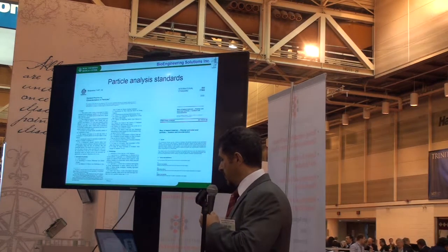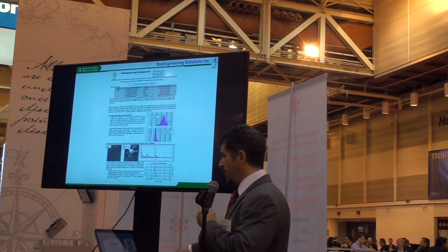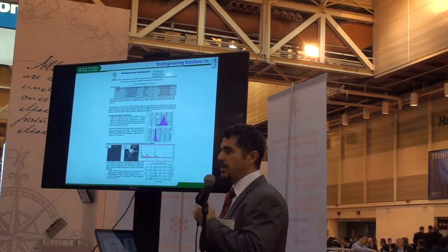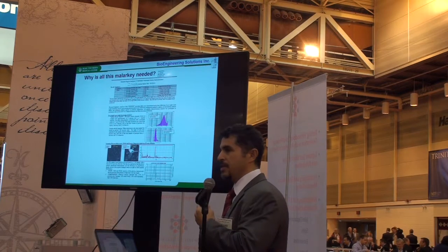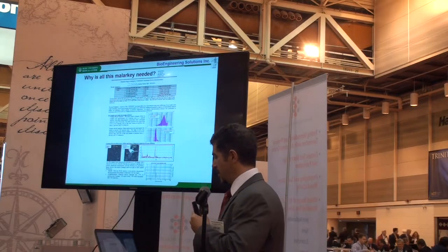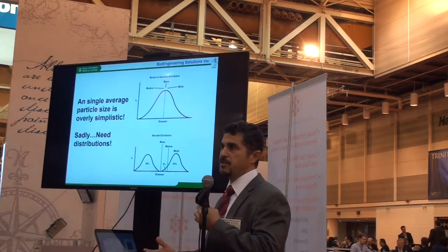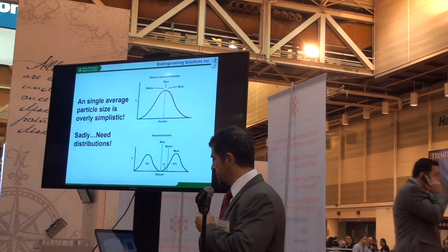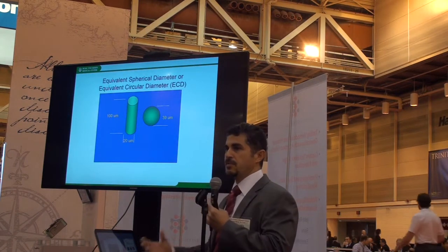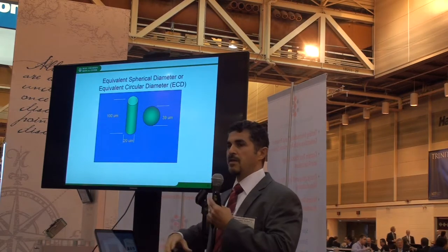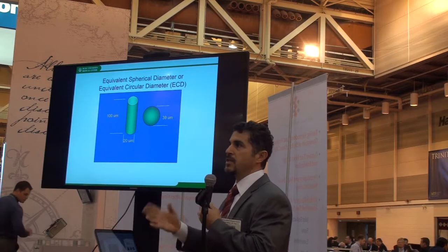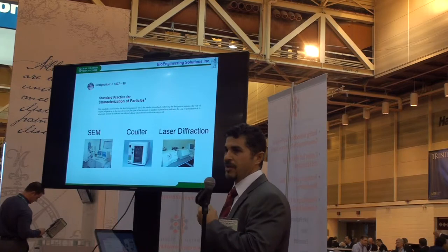How is debris characterized? There are ASTM and ISO guidelines that are fairly vague. When we do characterize debris, we produce reports with distributions of size based on number and volume. You might wonder why all of this is needed when you just want one particle size to submit to the FDA. The reason is that you can have quite different distributions with the same average particle size that would have different types of biologic reactivity. Not only that, but particles can have completely different shapes — and two particles can have the same volume and equivalent spherical diameter yet very different biologic reactivities when injected in vivo.